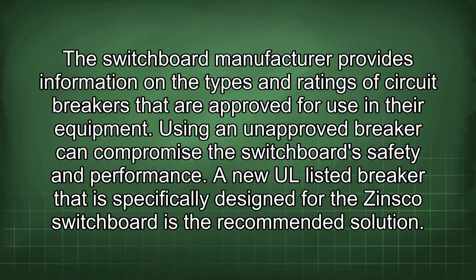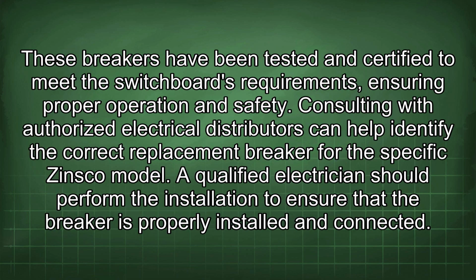A new UL-listed breaker that is specifically designed for the Zinsco switchboard is the recommended solution. These breakers have been tested and certified to meet the switchboard's requirements, ensuring proper operation and safety. Consulting with authorized electrical distributors can help identify the correct replacement breaker for the specific Zinsco model. A qualified electrician should perform the installation to ensure that the breaker is properly installed and connected.